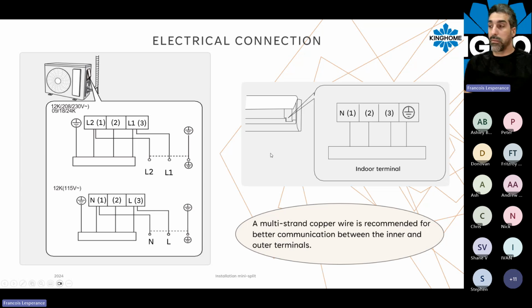It's always recommended to use a multi-strand copper wire for the connection between the indoor heads and the outdoor unit. This wire needs to be 600-volt insulated, PVC coated, and sunlight resistant, because you want to make sure the communication cable between those two units will hold up for the life of the unit. So it's very important to use a good wire and make sure your connections are good also. Talking about the communication, I can explain real quick how it works.